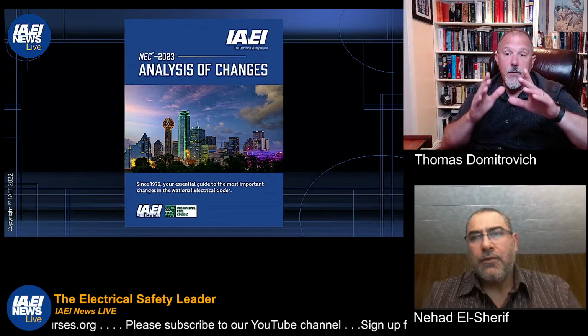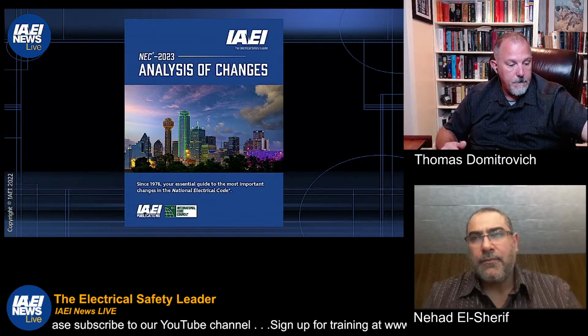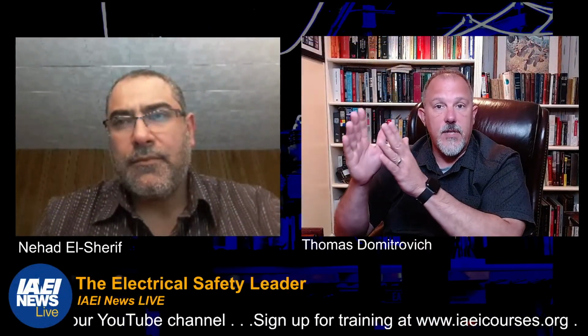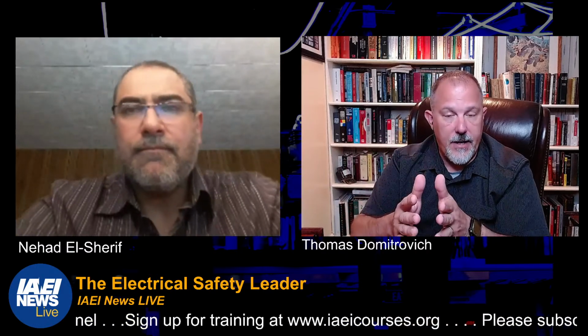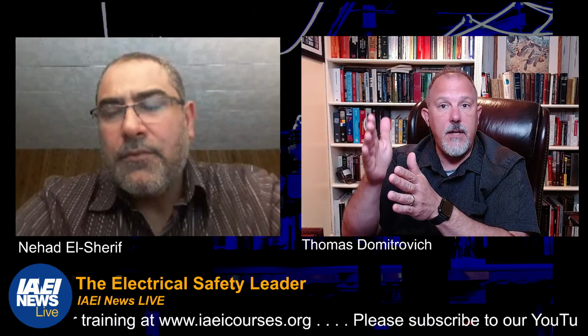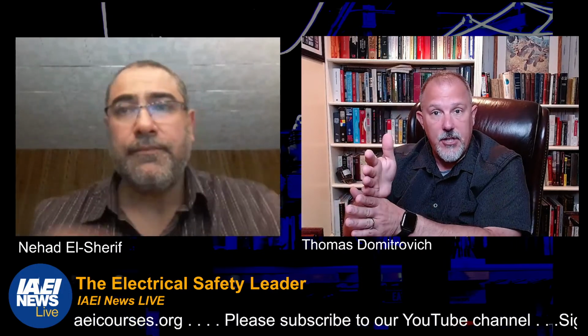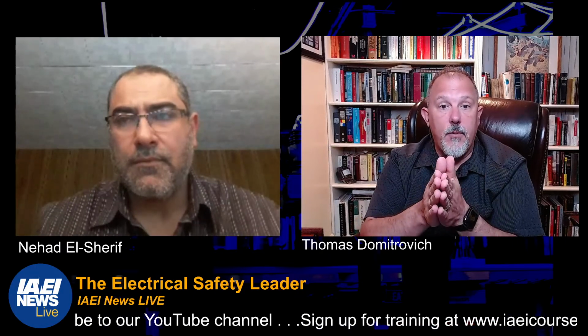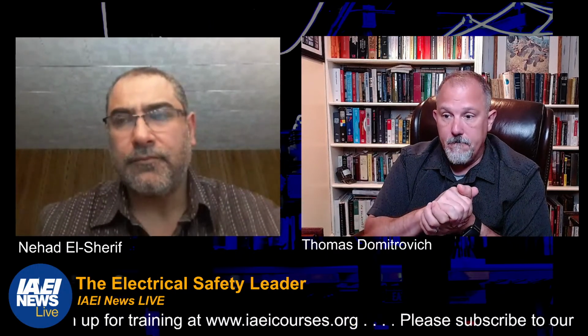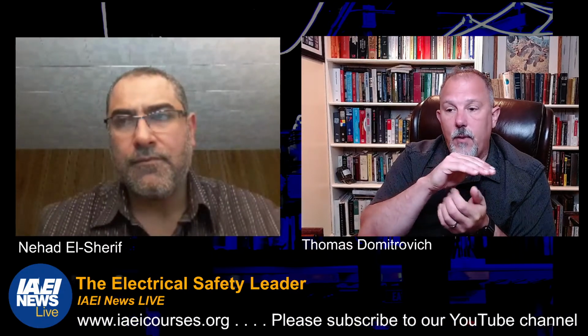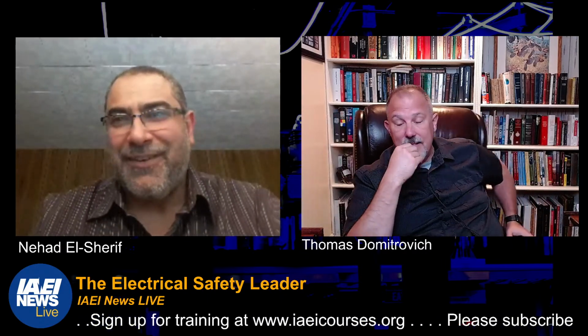So Nehad, we have covered what the difference is between a GFCI and a special purpose GFCI. We talked about the two different thresholds. We talked about the concept of let-go versus defibrillation. We spoke to the clearing times. We showed those curves. We talked about one of the important installation aspects of the special purpose, which is the equipment grounding conductor. And we even touched on where in the 2023 National Electrical Code they can find it. So hopefully we didn't miss anything. Can you think of anything that we missed before we close? I think we did good for an hour and 9 minutes. So I think we did pretty well.